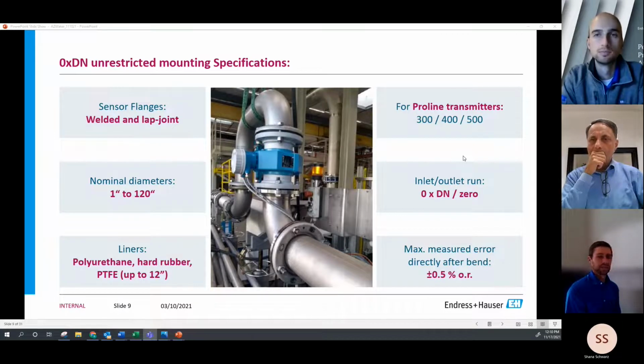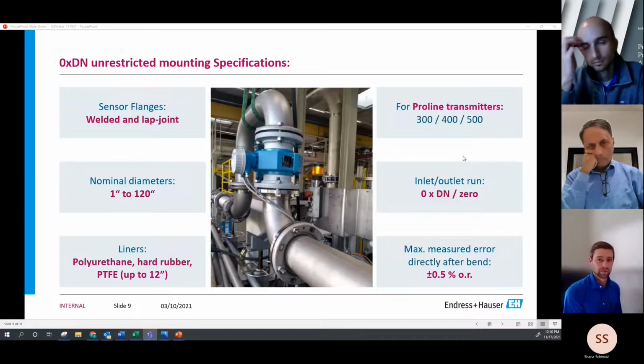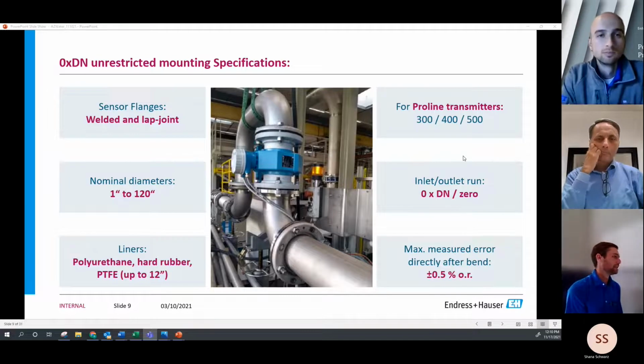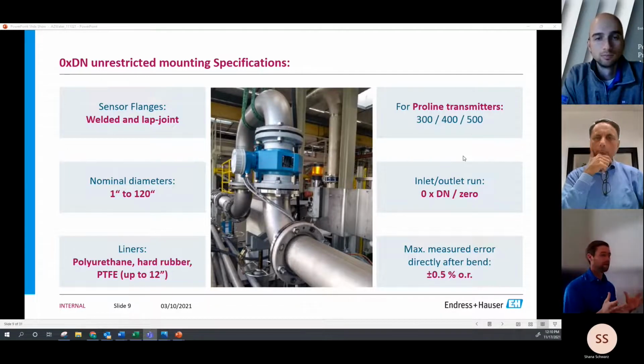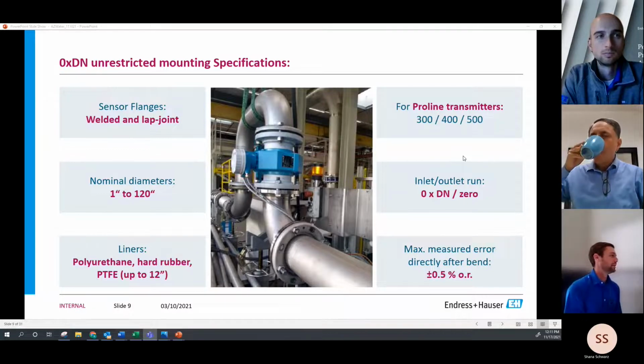And as far as process conditions, welded or lap joint. So these 0DN unrestricted mag meters, a lot of times they're specified for retrofit applications. And we're looking at how to fit a mag meter in a tight constrained area. And piping is there. It's already installed. The flanges are there. They're available. But if you get a meter with welded flanges, sometimes those bolt holes don't line up perfectly. That's where a lap joint would come in and help with solving that issue.